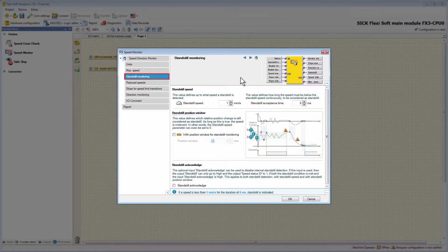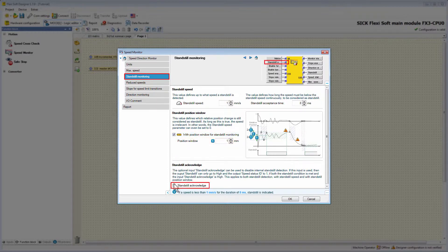Another option is the Standstill Position Window. By enabling the Position Window for Standstill Monitoring, you can define which relative position change is still considered as standstill — as long as this is true, the speed is irrelevant. There is also the possibility to enable the optional input Standstill Acknowledge, which extends the internal standstill detection by an external signal. Therefore, standstill will only be indicated at the output Standstill and SpeedStatusID if the standstill condition is met and the input Standstill Acknowledge is high.